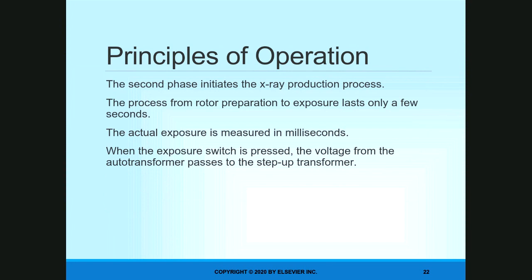When you prep the rotor, that's actually the first phase of a two-phase switch. That's why we call it a rotor exposure switch. So the first part takes care of the rotor spinning to speed and the electrons being released from the heated filament. The second phase of that switch is actually where X-rays are produced.